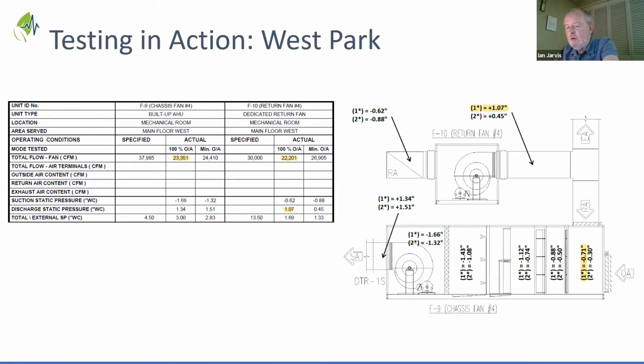And also when you're at 100% outside air, that minus 0.71 inches, if you're following me on the intake plenum, that's connected directly to the outside air. That's a big negative pressure. And sure enough, that air intake was plugged with debris and probably a bird's nest or two, and that was easy to clean and fix.